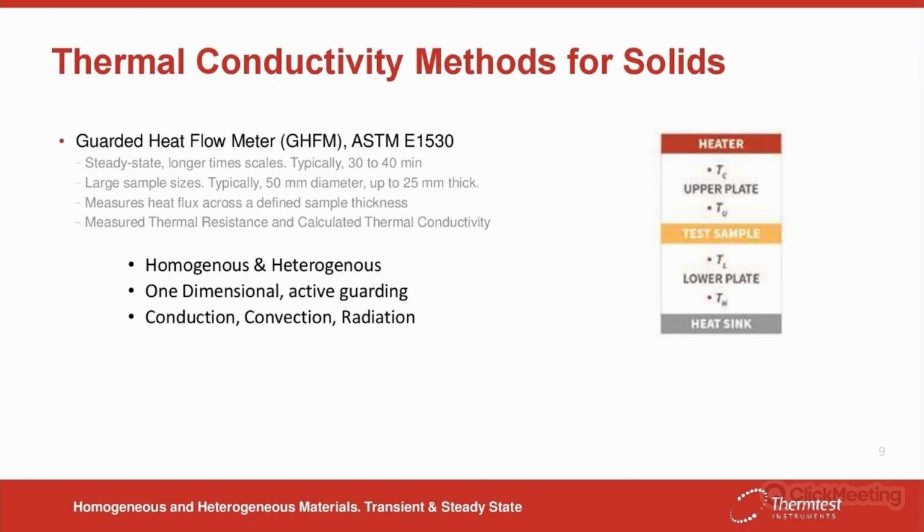A little bit about the scale of samples for a guarded heat flow meter: longer test times, as I mentioned, 30 to 40 minutes.